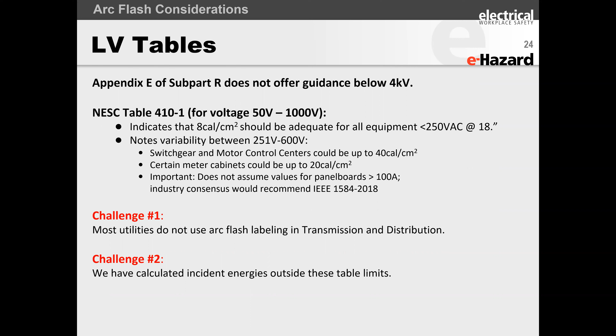The second challenge we have is that there have been white papers published where we actually show that these tables have limitations, right? If you look at some of the NFPA 70E tables, some of the NESC tables, when you come down to low voltage, because of the variances, now the tables have notes. You're not going to be able to take the IEEE to court and sue them for this because they've got notes, they've got exclusions, they tell you to use engineering judgment, etc. But if you are the poor person that accidentally took those tables without reading those footnotes, oh, by golly, you are going to be in so much trouble if something goes wrong.